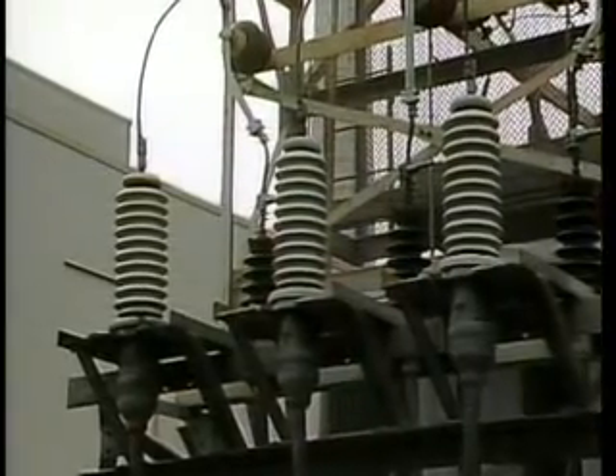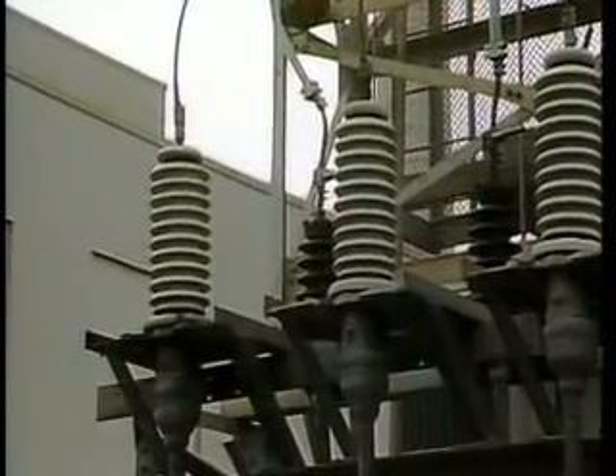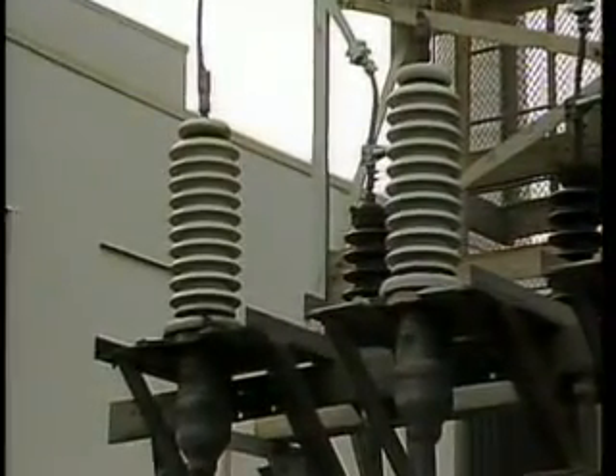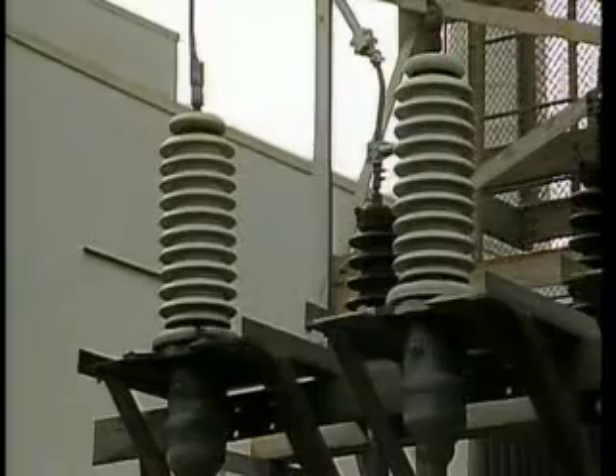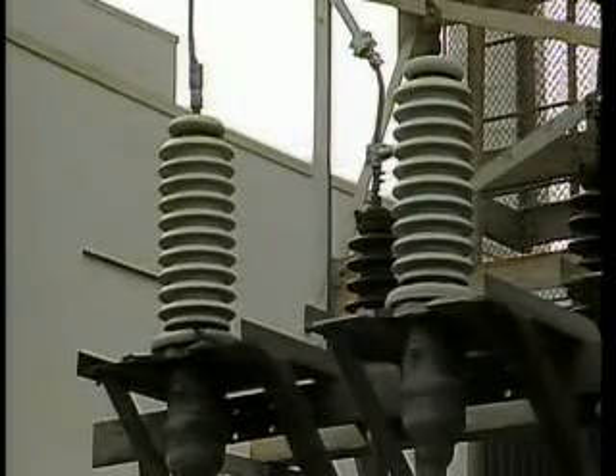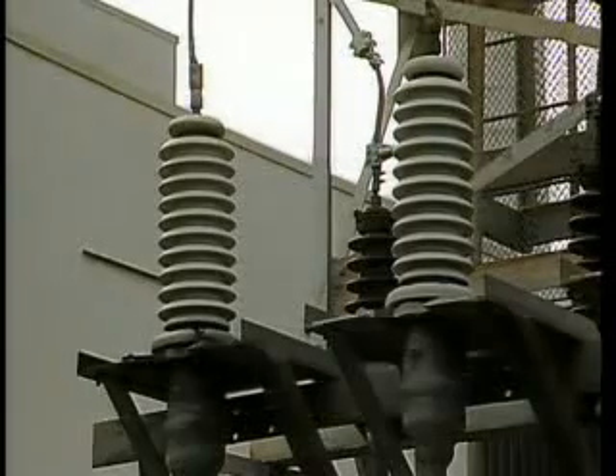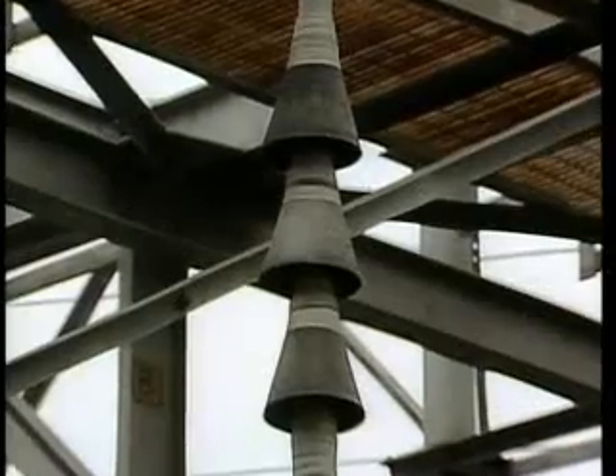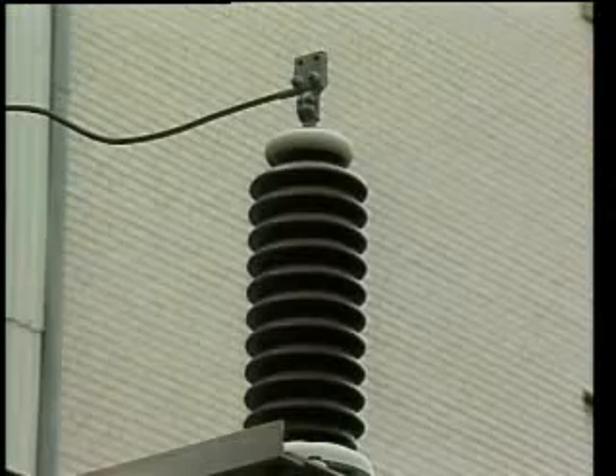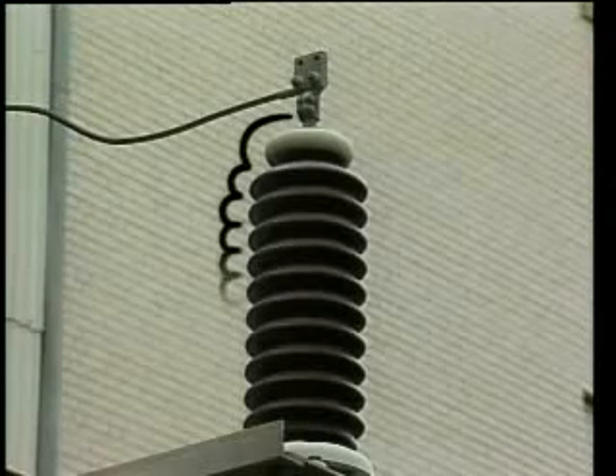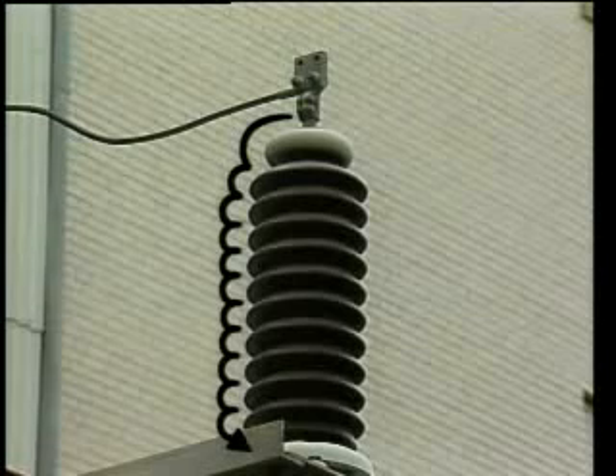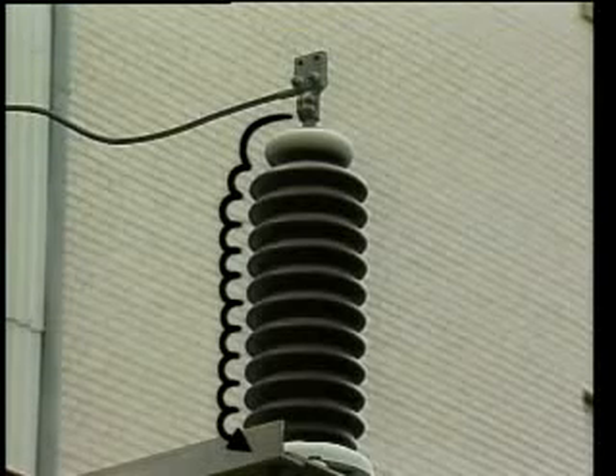Tracking is reduced or eliminated on high voltage terminations by using skirted tracking-resistant materials to cover the termination. Two common tracking-resistant materials used for high voltage terminations are porcelain and silicone rubber. The skirts increase the creepage distance between the energized conductor and the grounded insulation shield. The higher the voltage, the greater the size and number of skirts needed to prevent tracking.